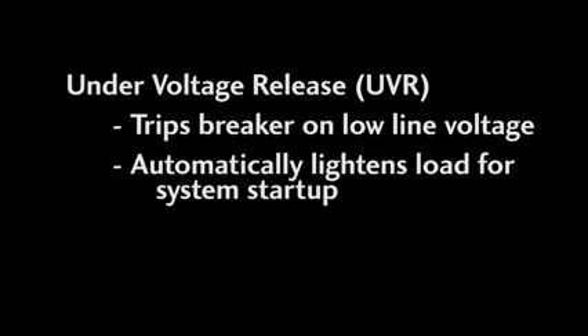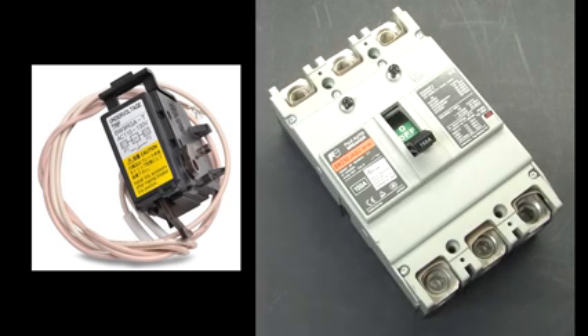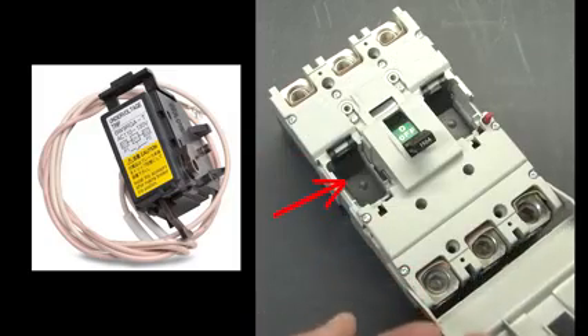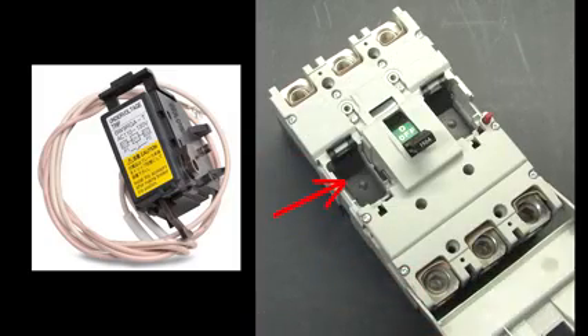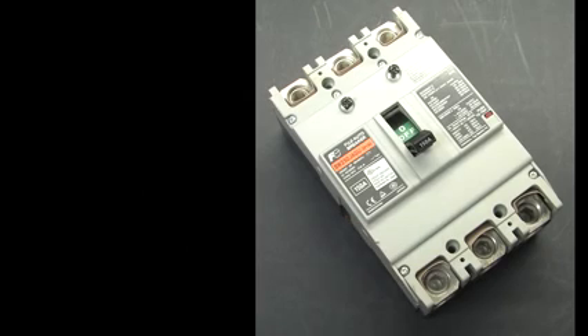An undervoltage release, or a UVR, trips the breaker when it senses line voltage is too low. This is handy when you have a system that shuts down and you want to be sure that the system isn't heavily loaded when it tries to start back up. The UVR will have tripped the breaker when the line voltage dropped, so when you go to bring the system back up, this load won't be a burden. Here's an example of a UVR for an MCCB. These are typically mounted inside the breaker here. Once the line voltage is back up, you then go manually reset the breaker.